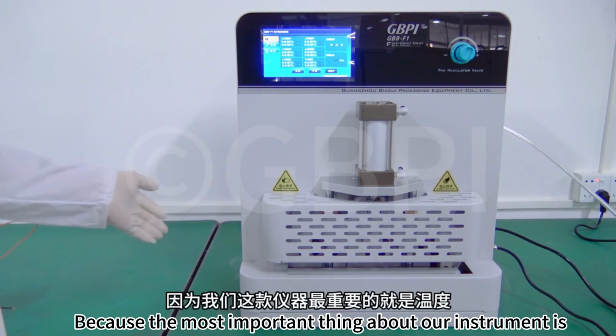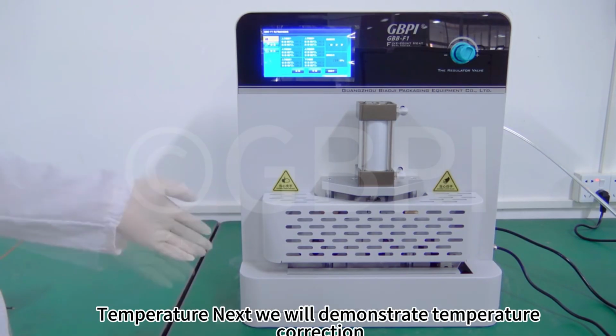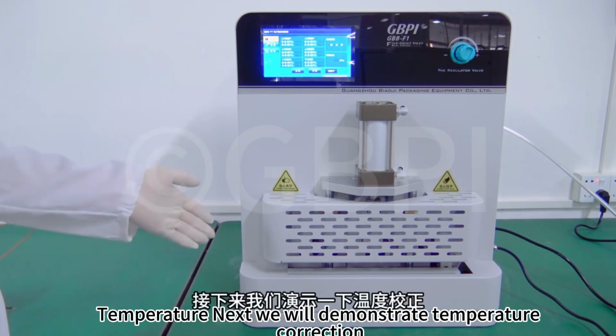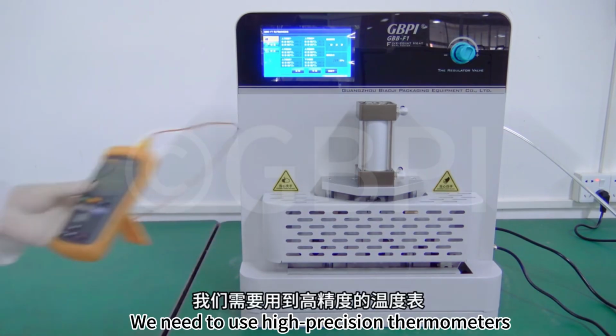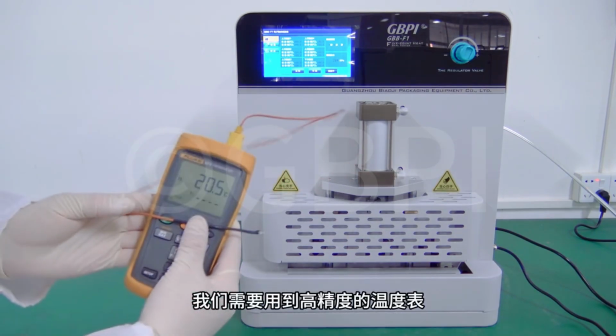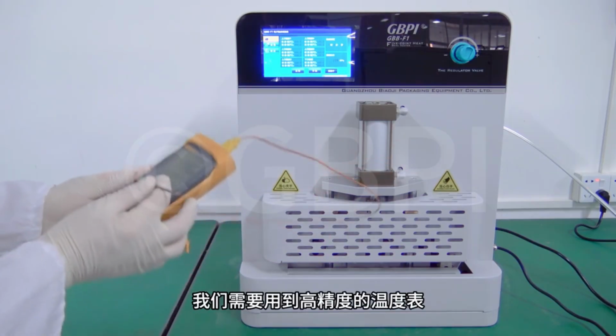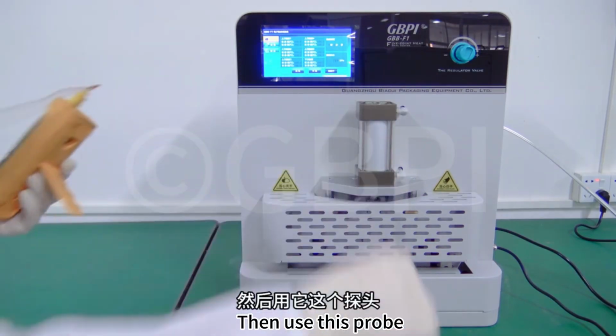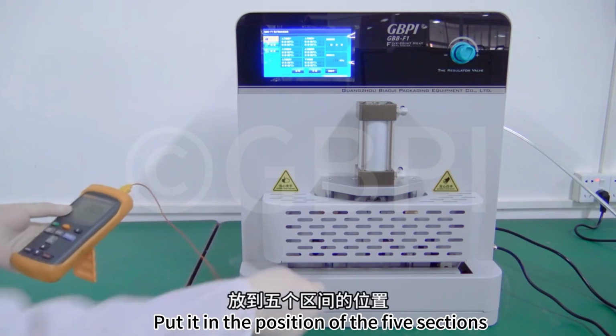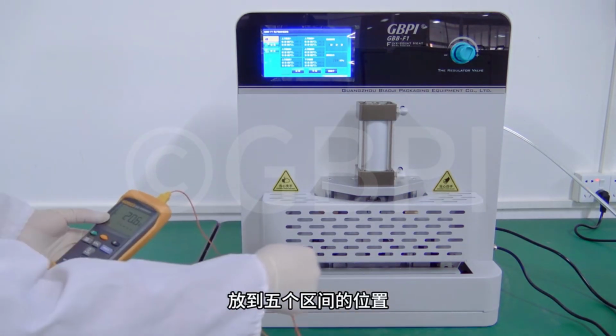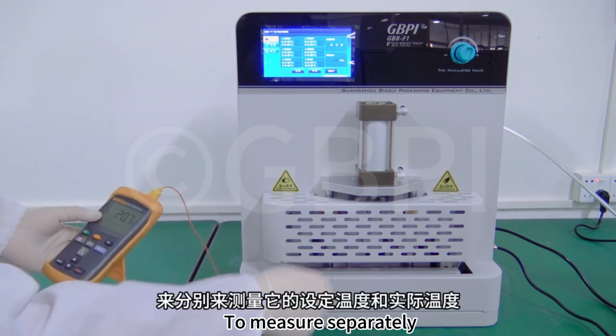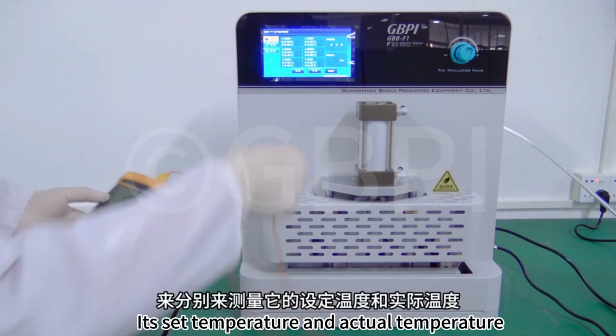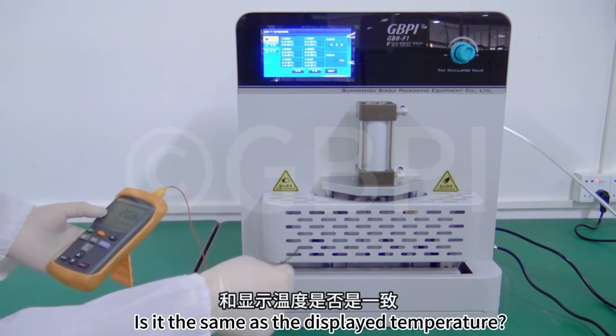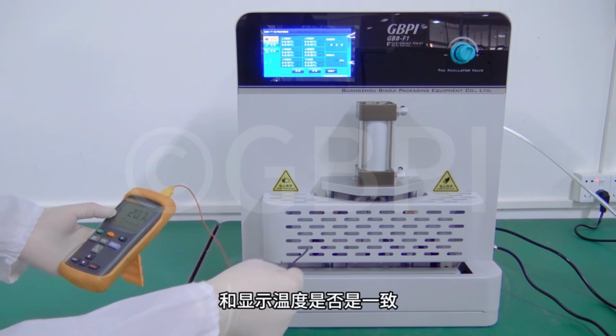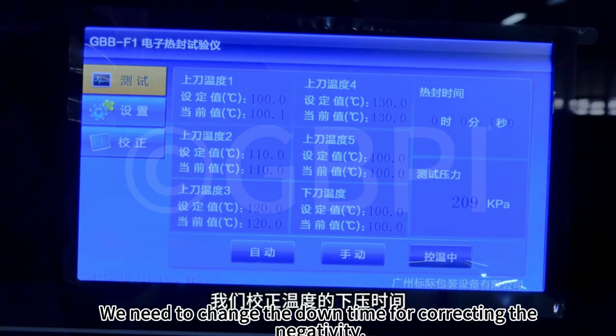Because the most important thing about our instrument is temperature, next we will demonstrate temperature correction. We need to use high-precision thermometers. Then use this probe. Put it in the position of the 5 sections. To measure separately, its set temperature and actual temperature. Is it the same as the displayed temperature? We need to change the downtime for correcting the negativity.